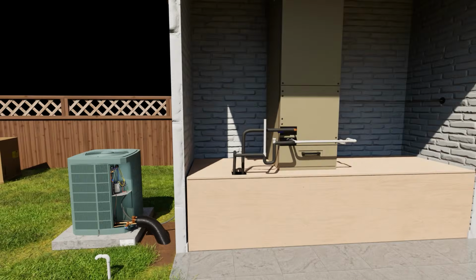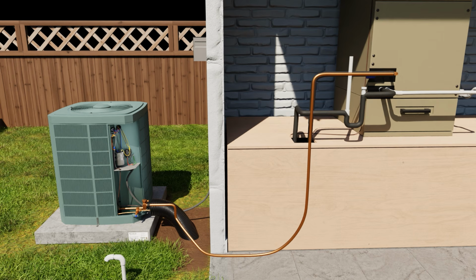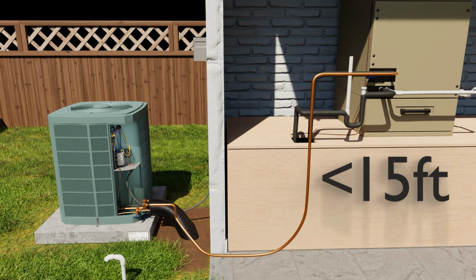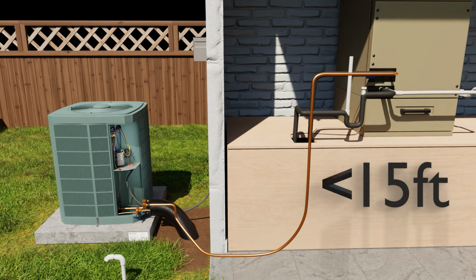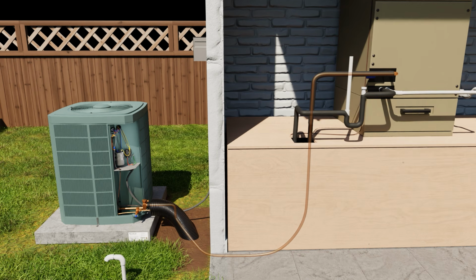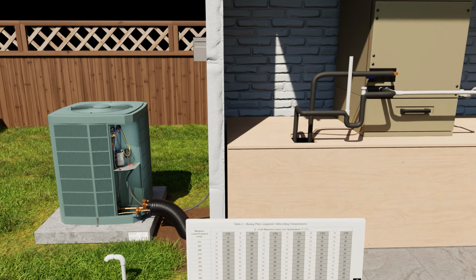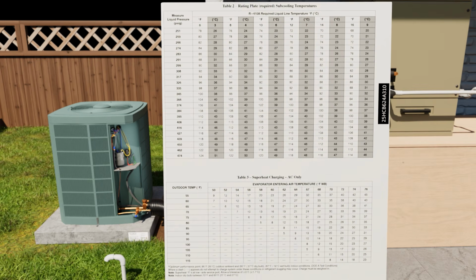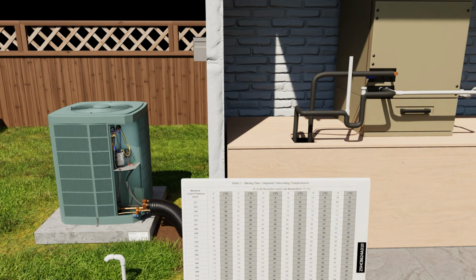Now we're prepared to run our condenser by setting down the temperature. Before we do, though, we want to take note of the line length, as well as the proper charging methodology for this system defined by the manufacturer. It's best to take both of these things into account. Generally speaking, you won't be adding any refrigerant charge unless your line length is over 15 feet. However, that's not always the case, especially in cases where the system has a microchannel condenser coil, so you need to follow your manufacturer's literature.